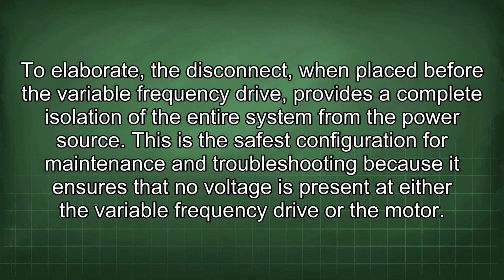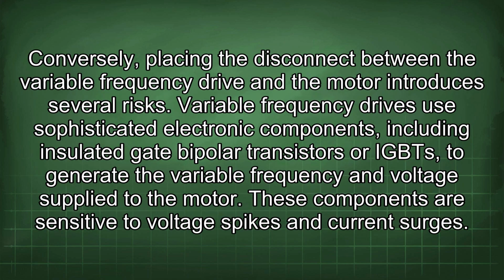disconnect. To elaborate, the disconnect, when placed before the variable frequency drive, provides a complete isolation of the entire system from the power source. This is the safest configuration for maintenance and troubleshooting because it ensures that no voltage is present at either the variable frequency drive or the motor. Conversely, placing the disconnect between the variable frequency drive and the motor introduces several risks.